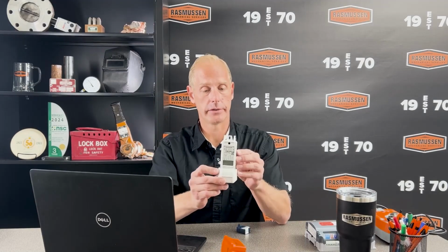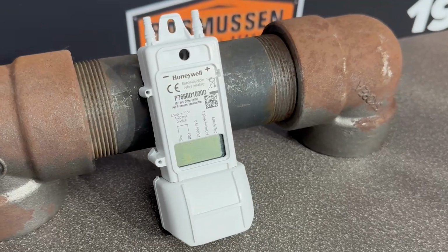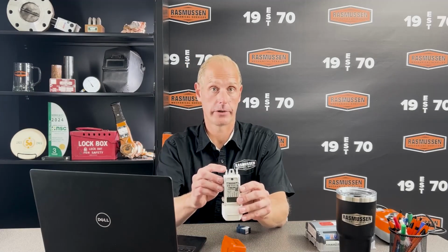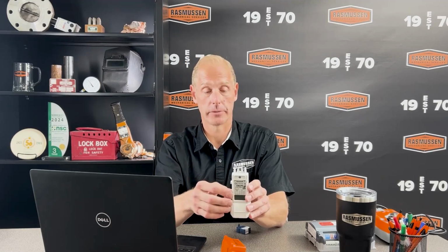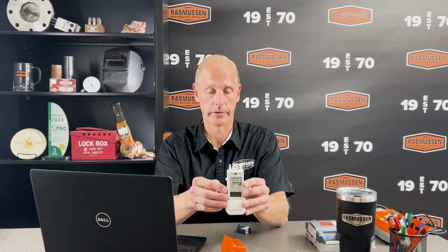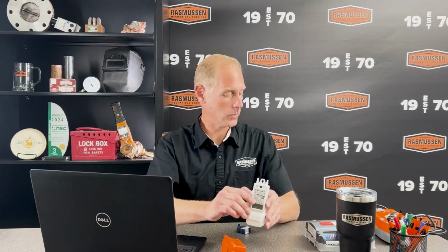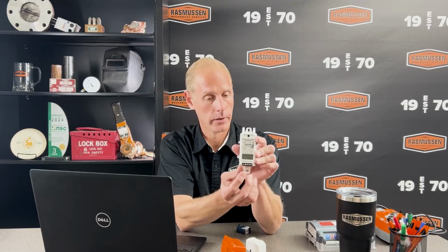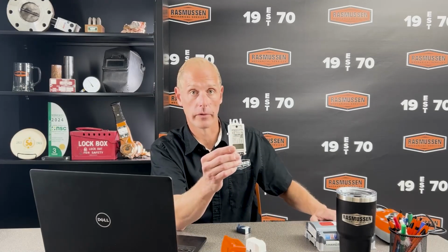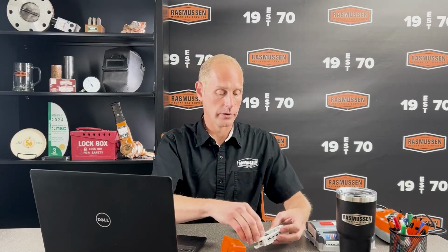This right here is a differential pressure sensor. This is going to read air pressure in your ductwork, or possibly just in your building to find out the air pressure in your building. Again, this has these little terminals right here, and it's going to wire back to one of our inputs on our controller. So those are examples of analog sensors because they send a signal that is variable across a scale.